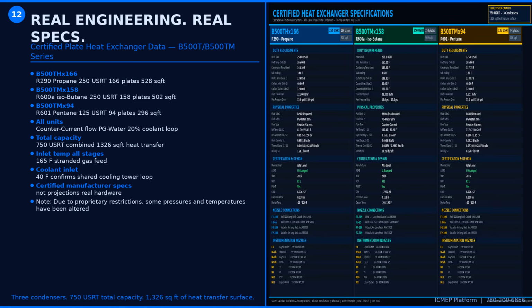Every claim in this presentation is backed by real engineering. Here are the actual certified specifications for the plate heat exchangers at the heart of the ICMEP Cascade fractionation system. Stage 1, propane recovery. The B500THx166 condenser. Refrigerant R290, pure propane. 250 U.S. refrigeration tons of heat transfer capacity. 166 plates. 528 square feet of heat transfer surface area. Coolant, propylene glycol water, 20%.